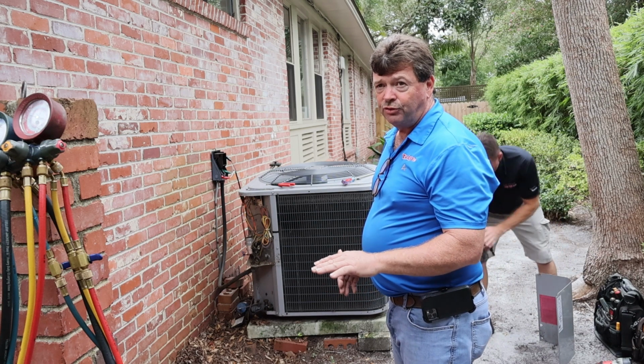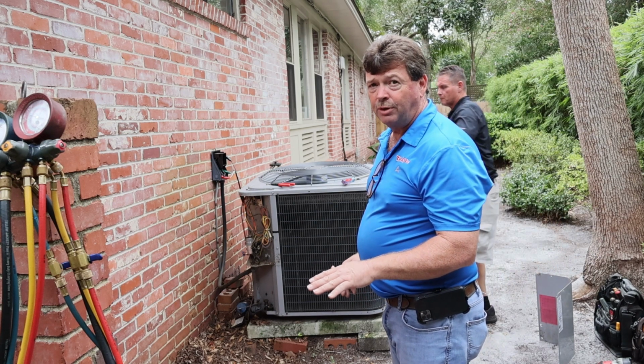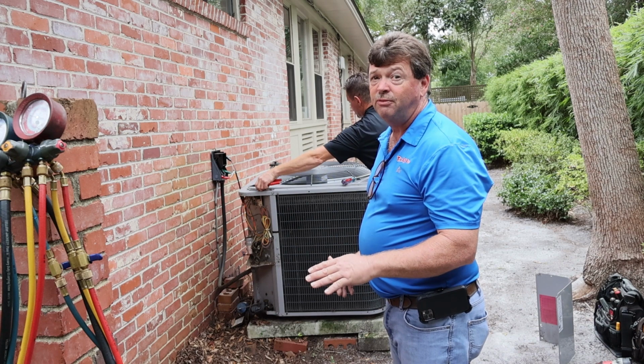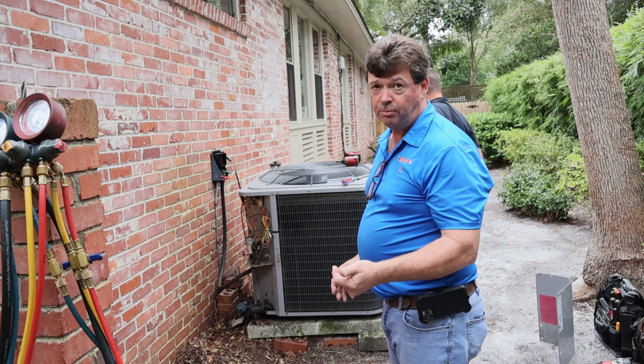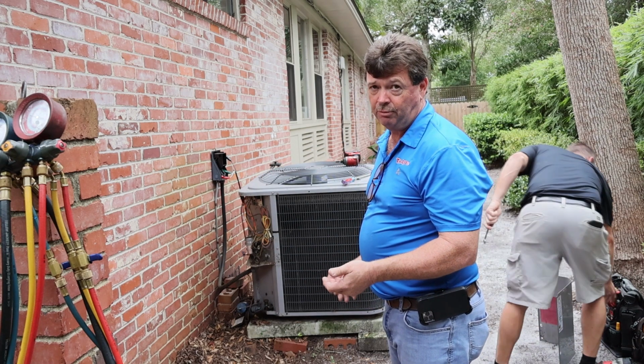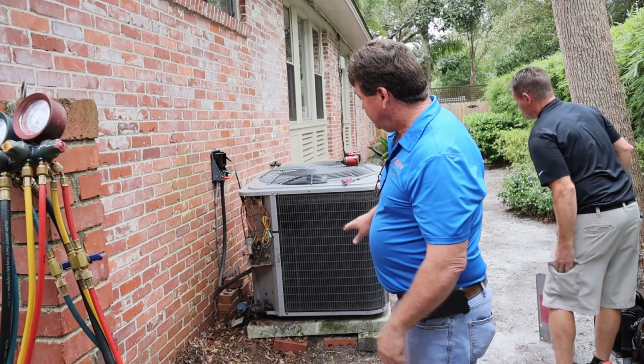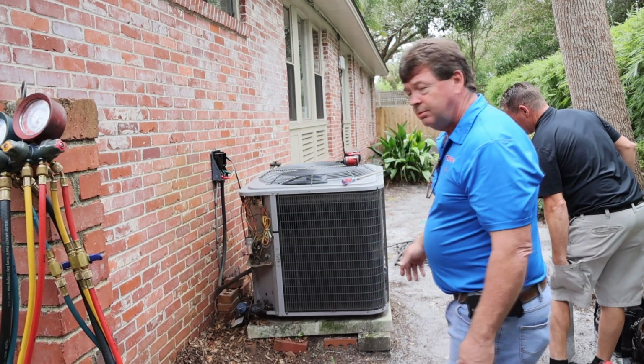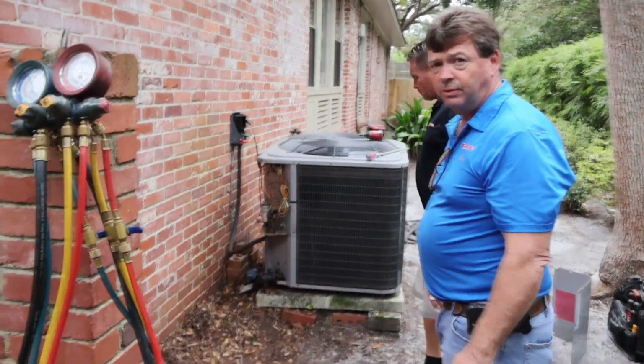You get some of the parts that may not be getting lubricated properly, could fail prematurely, and a compressor replacement's not a cheap repair. So pay attention to that. It does need to be leveled, and we'll address that with the customer.